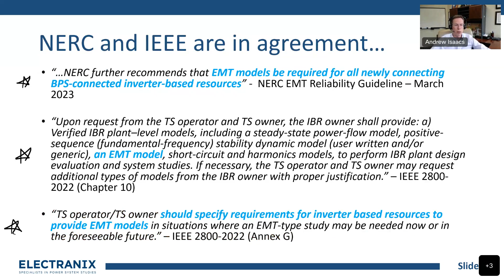And then further in Annex G, where they talk in more detail about what those should look like, it says that the TS owner should specify requirements for those inverter-based resources to provide EMT models in situations where an EMT study might be needed. So, going back here -- this is our NERC recommendation, and the IEEE 2800 text, and then Annex G of that 2800 standard says that the TS owner should specify requirements for inverter-based resources to provide EMT models.